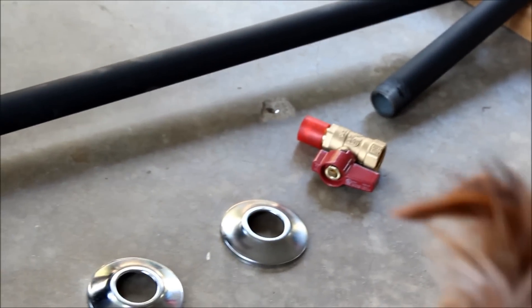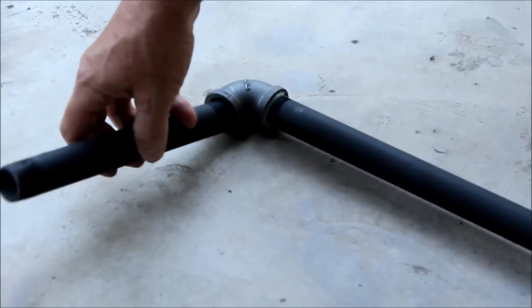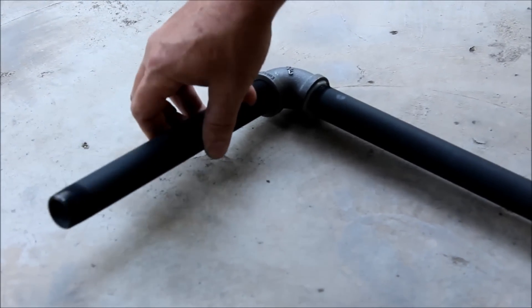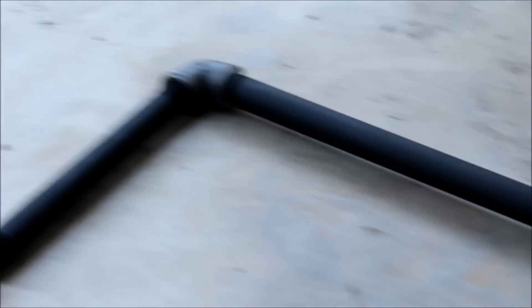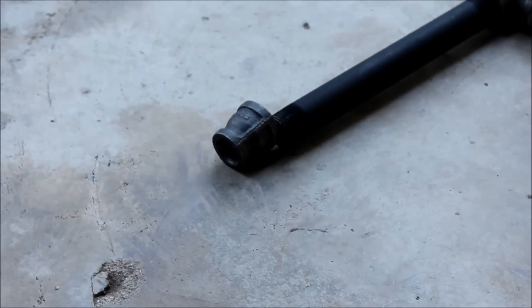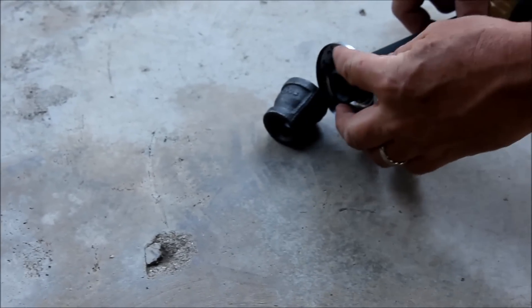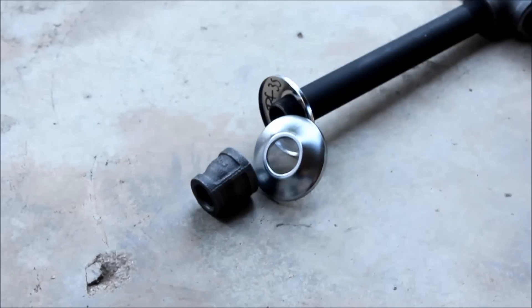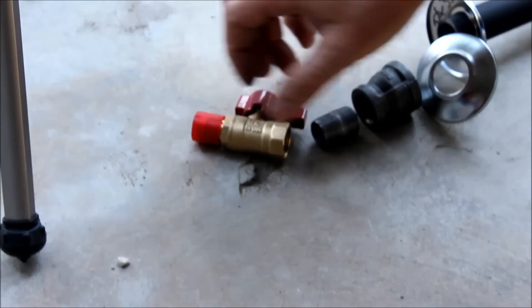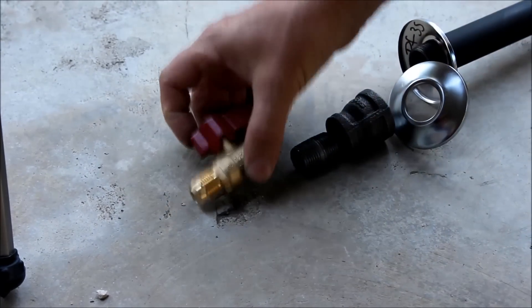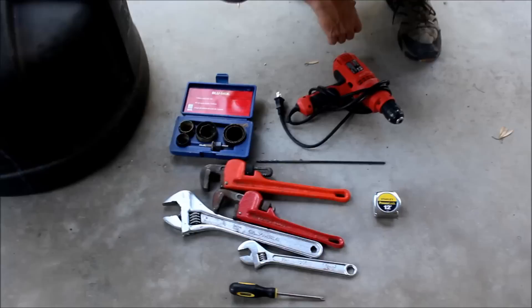Now on that pipe on the roof, I'm going to come down using this. And then this one here is going to connect on the nipple, I mean on the elbow. And the elbow is going to go to a reducer. This here will be on the wall on one side. This will be on the wall on the inside. It'll go reducer, then nipple, then it'll go here onto the flare fitting. And then this one will go onto our flexible gas line.